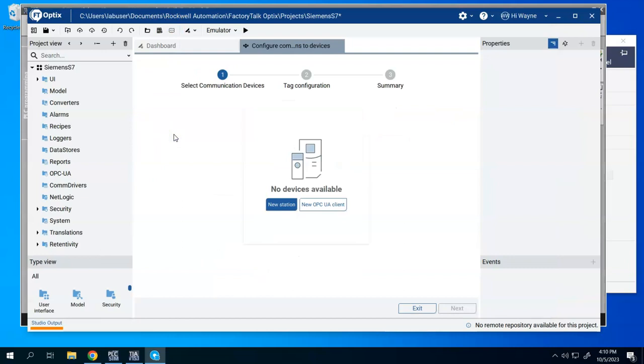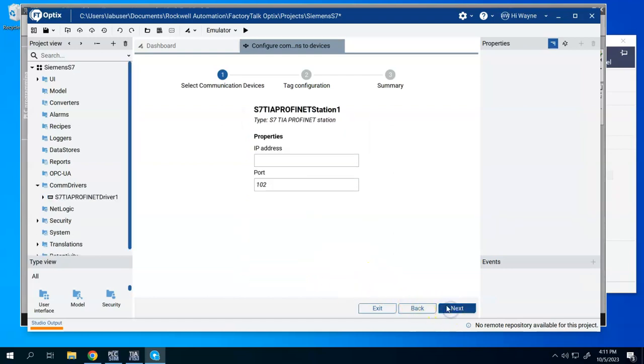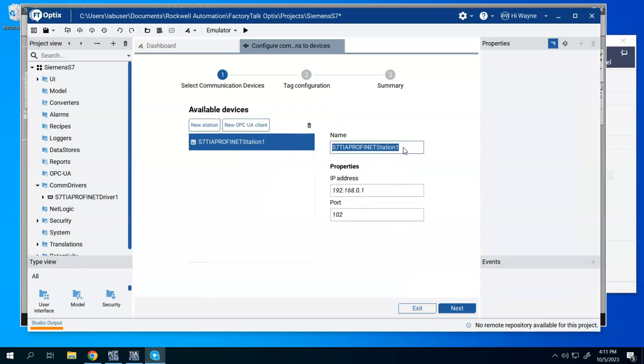So I'm going to go with the configured communications. I'm going to say new station. I'm going to go ahead with the TIA PROFINET station. Hit next. I'll type in the IP address of our simulator. Leave the port at 102. Now I can rename this. Again, this is just a name for the CPU itself. I can just type in PLCSIM and hit next.